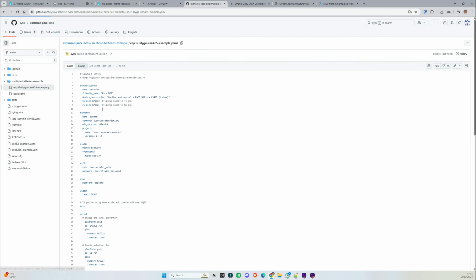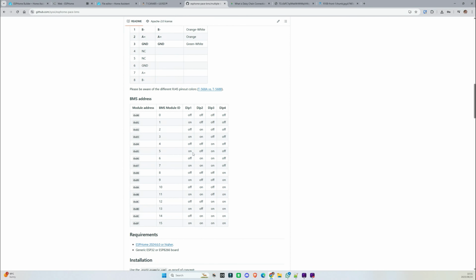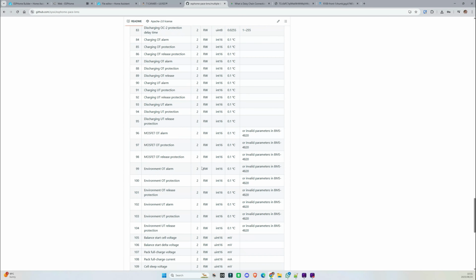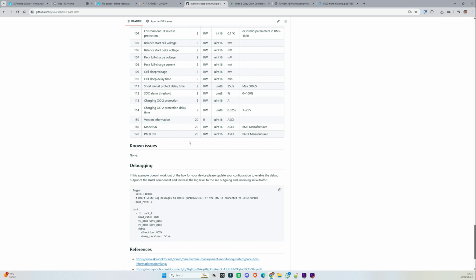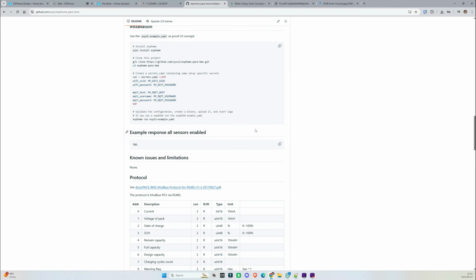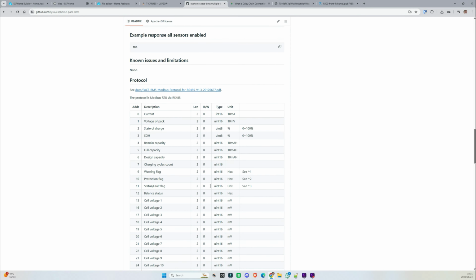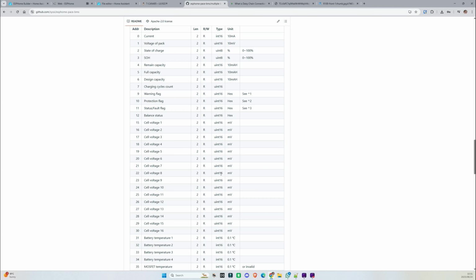If you look back over here, in each battery there are about 120 entities you can query, or addresses you can query on the Modbus register. So if you're querying each battery and you've got 5 batteries, that's 600 queries on a 9600 baud rate connection. Your update time is going to start slowing down, you're not going to have a live connection. It'll take 2 or 3 minutes to connect. I'm sure you can work it out exactly.